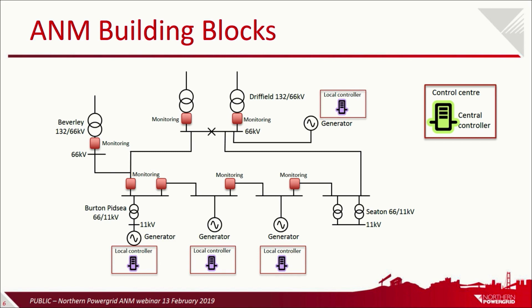So we also have installed some local controllers at each of the generator sites that are contributing to these constraints. These could obviously be demand customers in future. If a customer has some controllable demand, we can use ANM to control that demand too. It doesn't have to be generation that we're controlling. And in the Driffield instance, they're monitoring the generator behaviour, and they pass on the target export set points that the central controller back at our control centre sends to them. So they're looking after the generators locally, if you like.